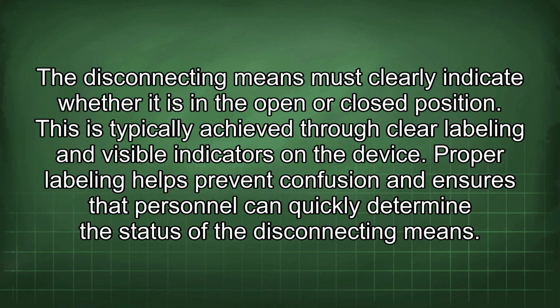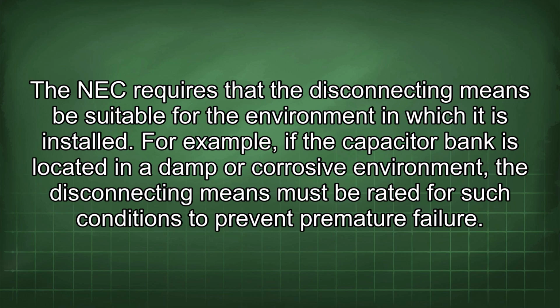The disconnecting means must clearly indicate whether it is in the open or closed position. This is typically achieved through clear labeling and visible indicators on the device. Proper labeling helps prevent confusion and ensures that personnel can quickly determine the status of the disconnecting means. The NEC requires that the disconnecting means be suitable for the environment in which it is installed. For example, if the capacitor bank is located in a damp or corrosive environment, the disconnecting means must be rated for such conditions to prevent premature failure.